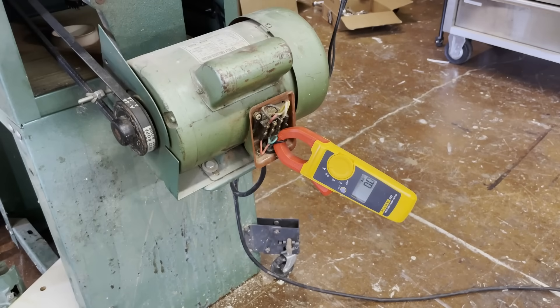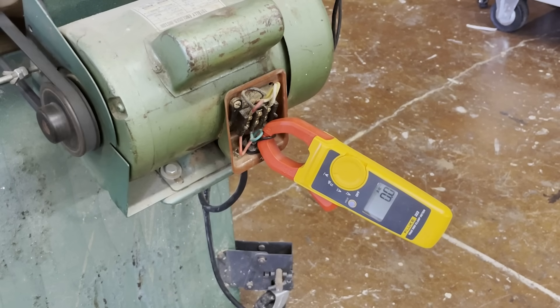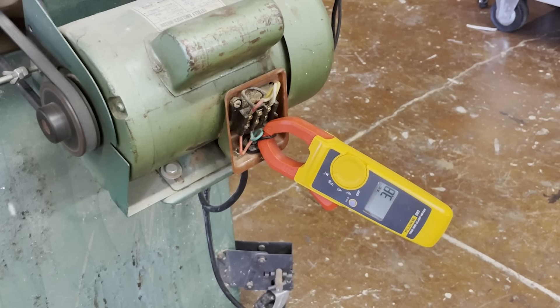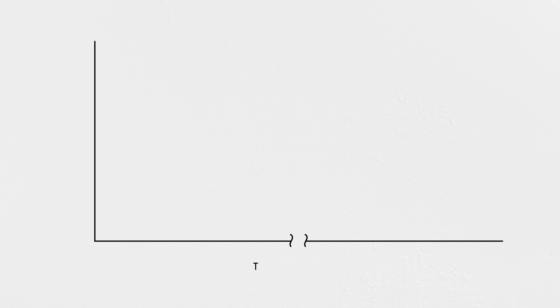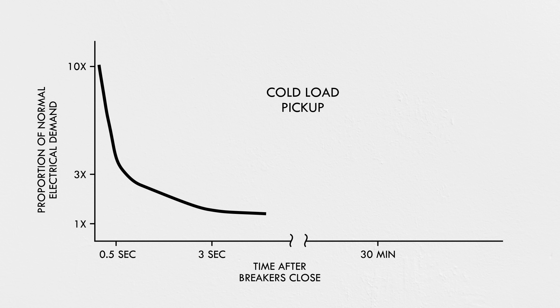And don't forget that many of these appliances use inductive motors that have huge inrush currents. Here's an ammeter on the motor of my table saw while I start it up — it draws a whopping 28 amps as it gets up to speed before settling down to 4 amps at no load. Imagine the demand from thousands of motors like this starting all at the exact same instant. The technical term for this is cold load pickup, and it can be as high as 8 to 10 times normal electrical demands before the diversity of loads starts to average out again, usually after about 30 minutes.